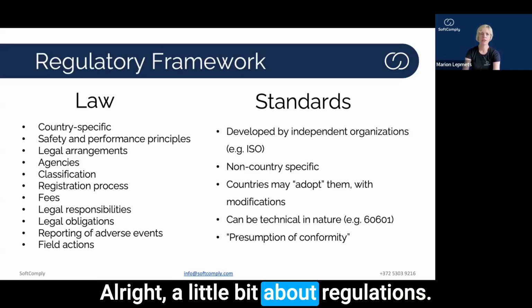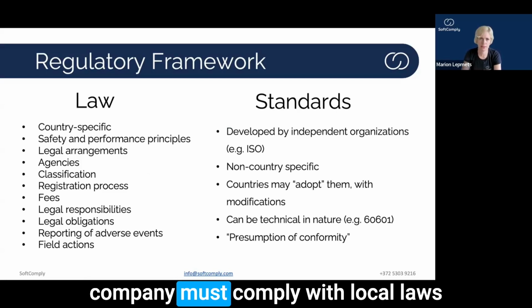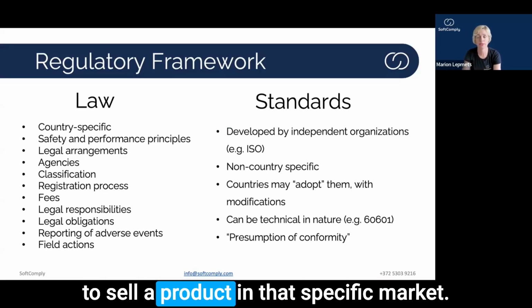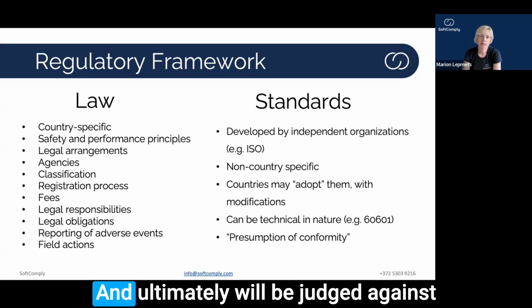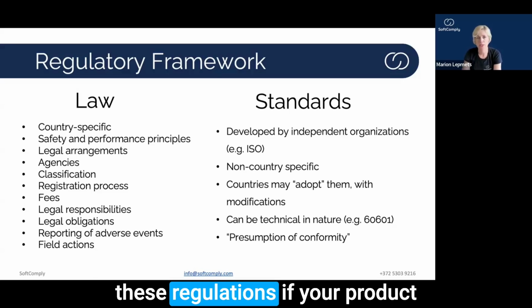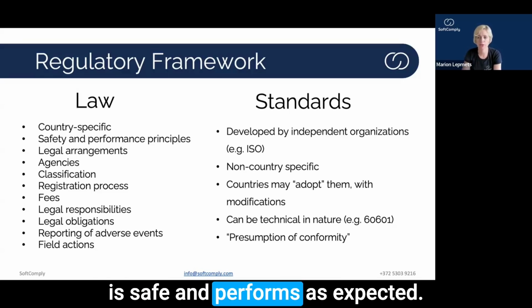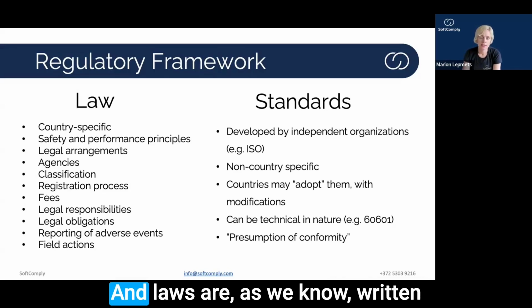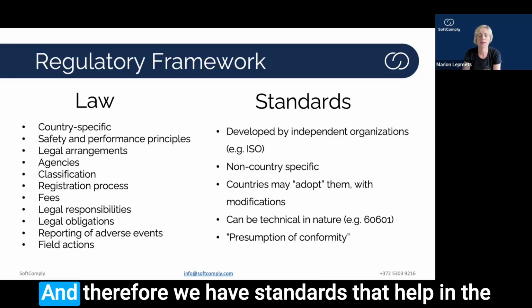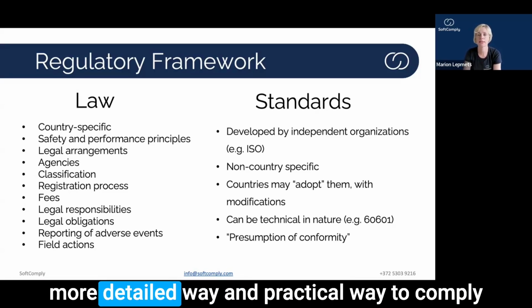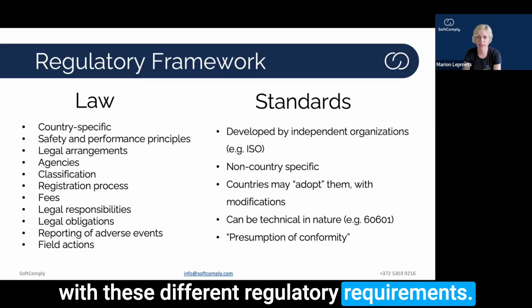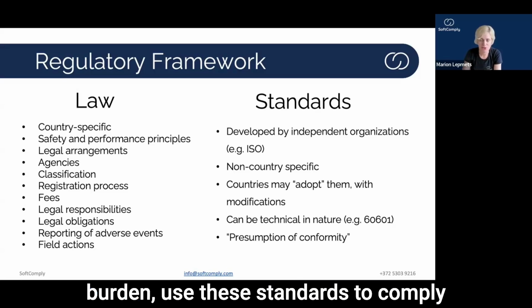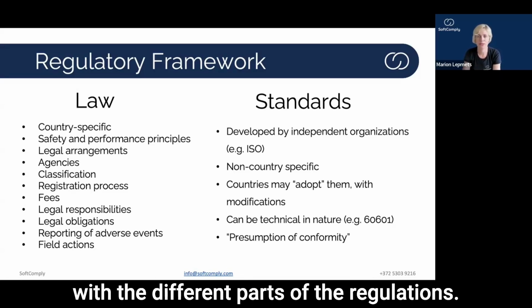All right, a little bit about regulations. In the medical device world, the company must comply with local laws to sell a product in that specific market. And ultimately, you will be judged against these regulations if your product is safe and performs as expected. And laws are, as we know, written in a quite abstract manner, and therefore we have standards that help in a more detailed and practical way to comply with these different regulatory requirements. So rather than seeing standards as a burden, use these standards to comply with the different parts of the regulations.